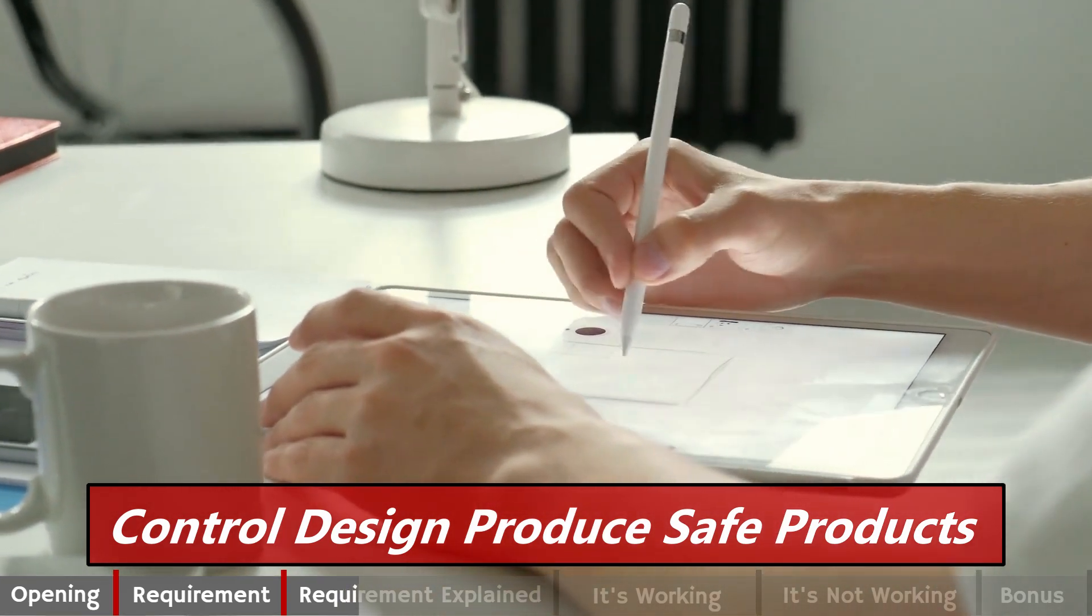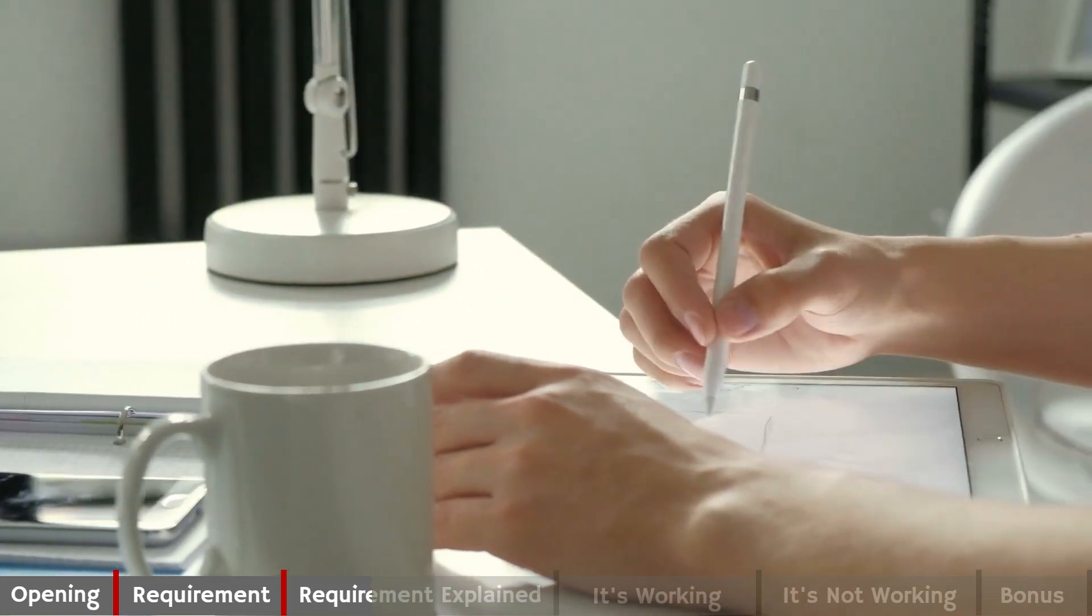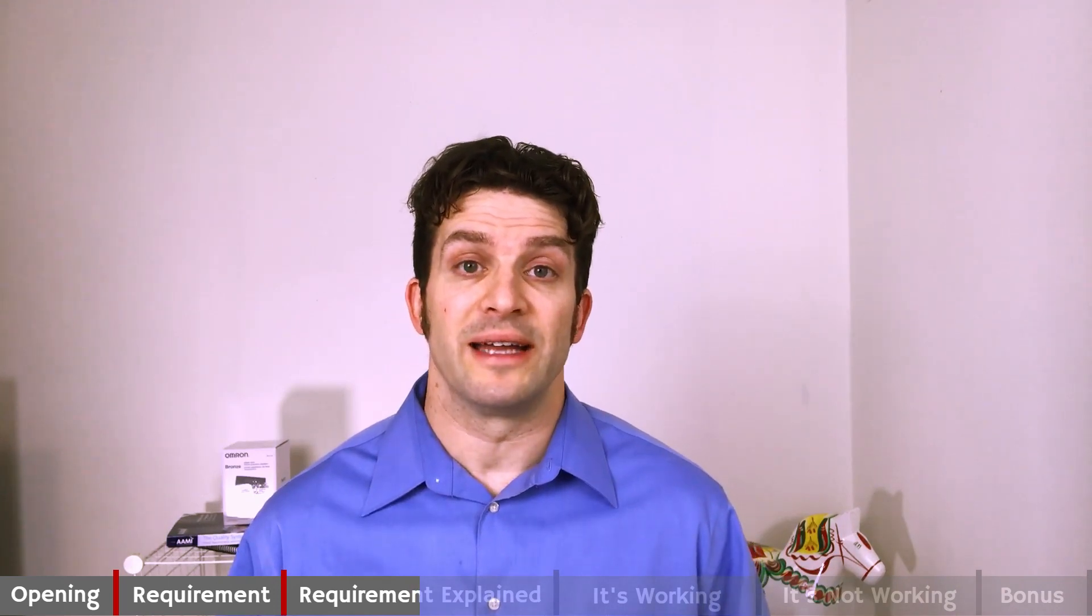Design controls are intended to control the design process so that we produce a safe and effective medical device. In order to do that, we have to have a procedure that defines the design process that we will follow. The procedure must cover the 10 requirements that are outlined in both 820 and 13485.